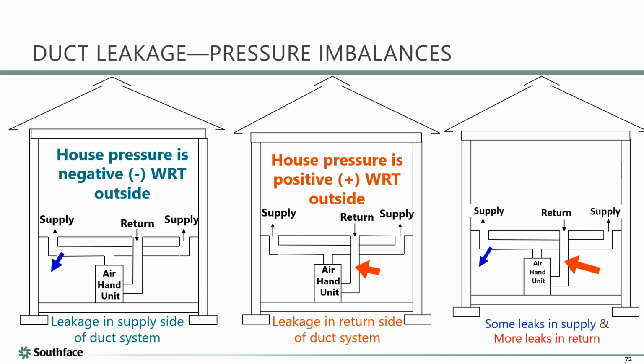So this is sometimes called the dominant duct leakage. Just really quickly, if this air handler is blowing 1,000 and it loses 100, that means 900 goes in. But because of this return leak, 300 from there, only 700 from the house. The dominant duct leak in this case is the return leak. It's the bigger one, so the house pressure is going to go positive.